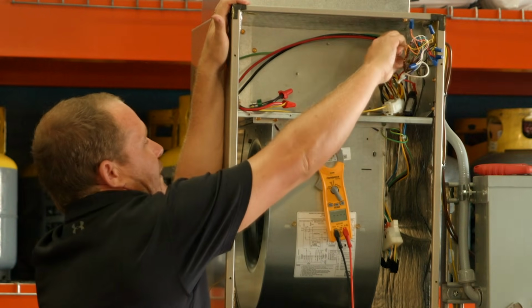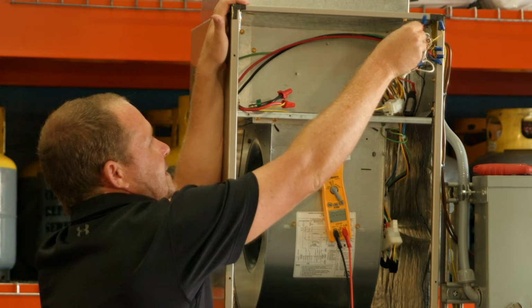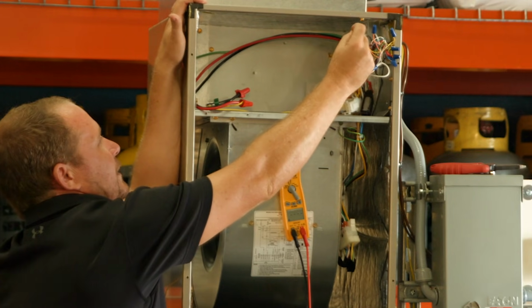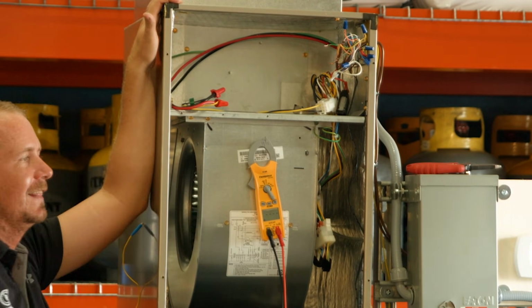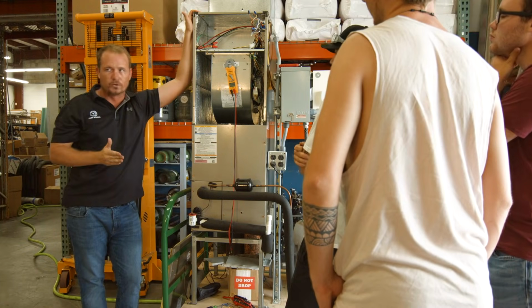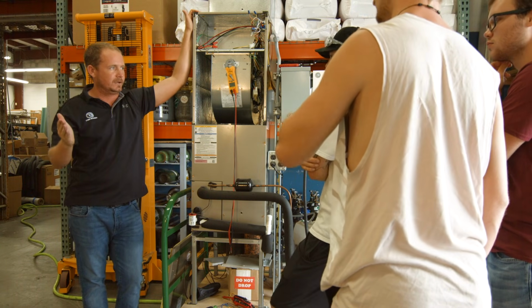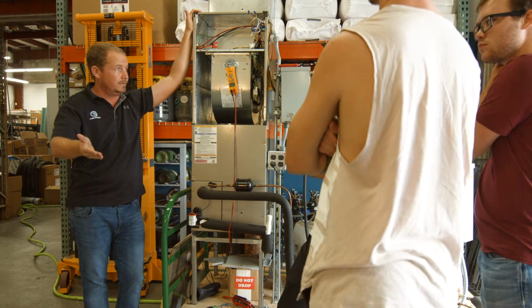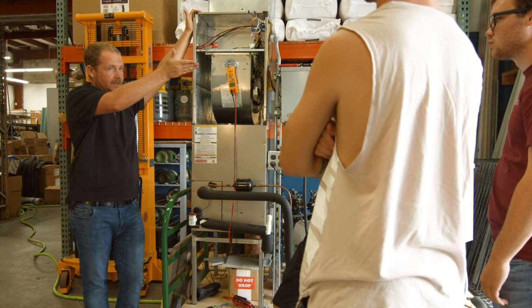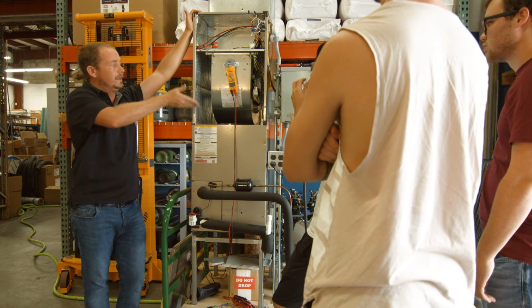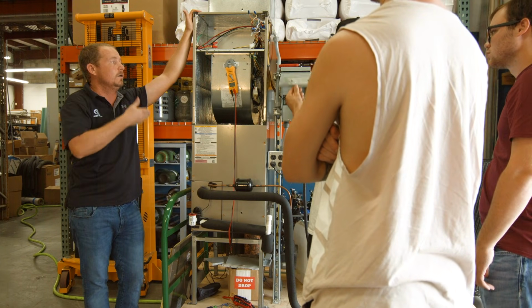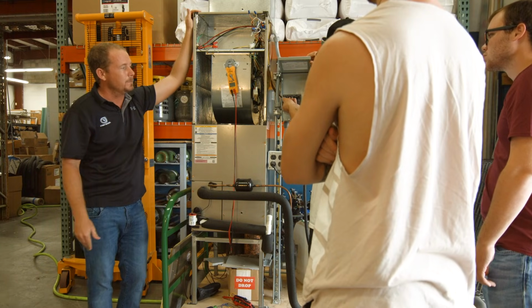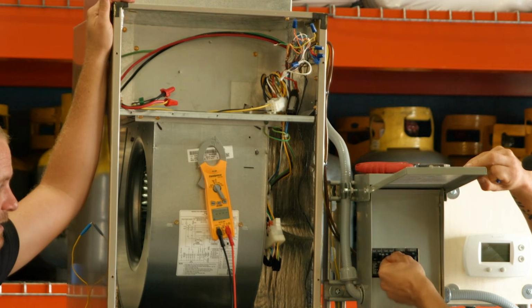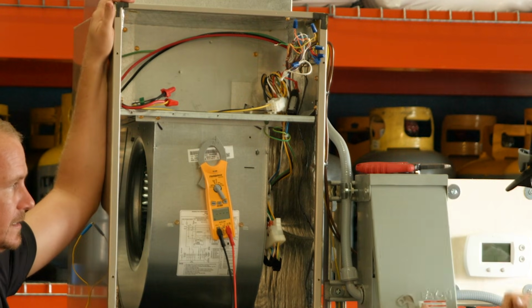Okay, so now before we energize in this case - and this is the same kind of test you do, what we call the redneck test on your compressor - it's like the last test you do to make sure that is the circuit, because before it was tripping the breaker. Now we're going to go ahead and energize it. Safety glasses on, energize it, and see if now with G disconnected, does everything else run as expected and energize?